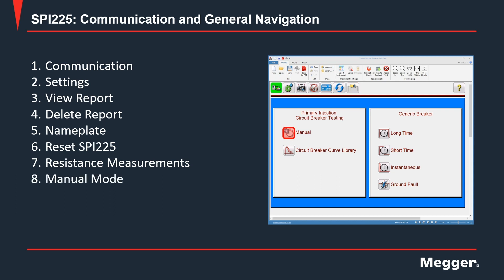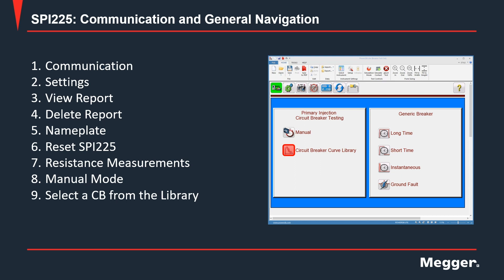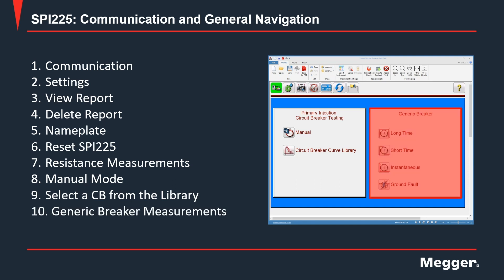Going down to the primary injection circuit breaker testing section of the home screen, the first button — manual mode — will let you control the unit in fully manual operation. The next option will allow you to define which circuit breaker you are testing from a library of about 7,000 circuit breakers from different manufacturers. And finally, if the breaker you are testing is not in the library, you can still perform the measurements using the generic breaker functions.